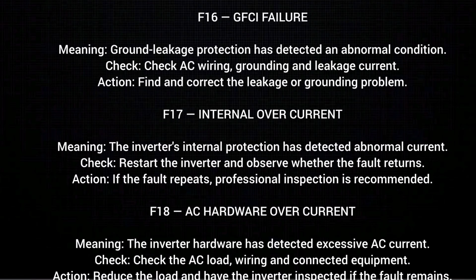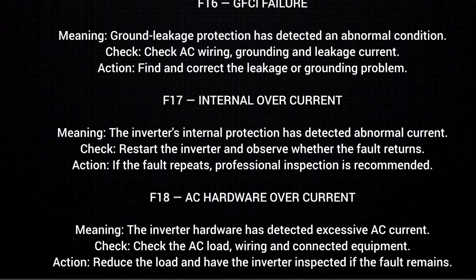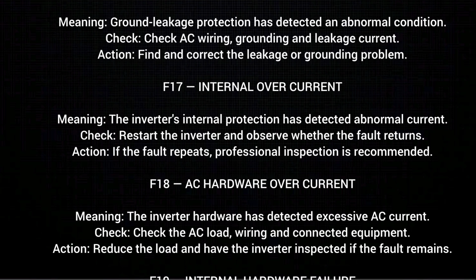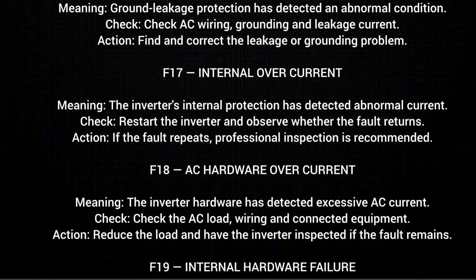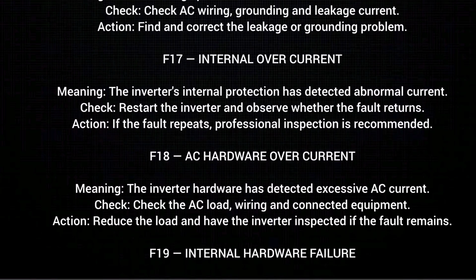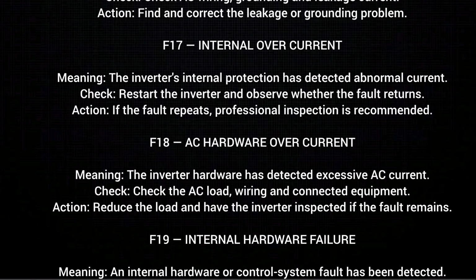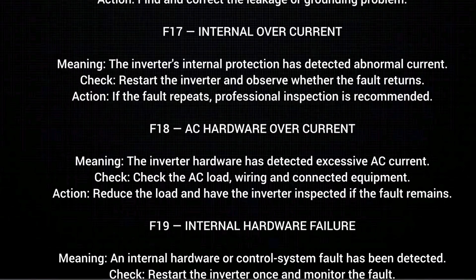F17 Internal overcurrent, meaning the inverter's internal protection has detected abnormal current. Check. Restart the inverter and observe whether the fault returns. Action. If the fault repeats, professional inspection is recommended.